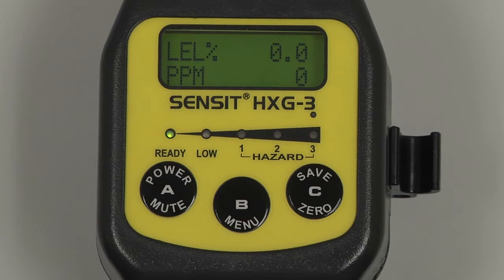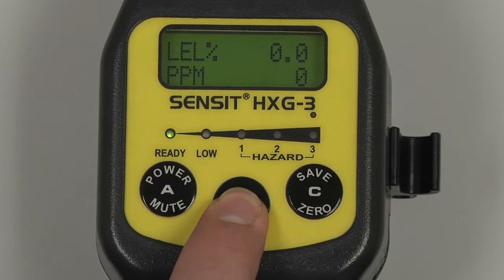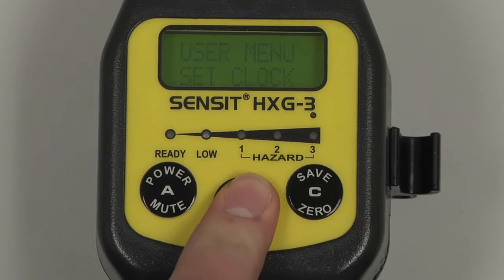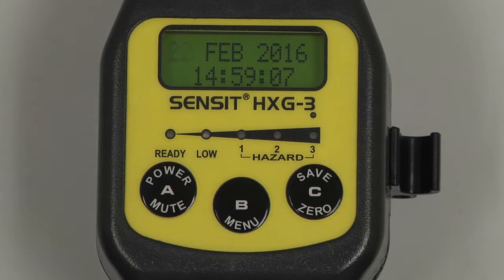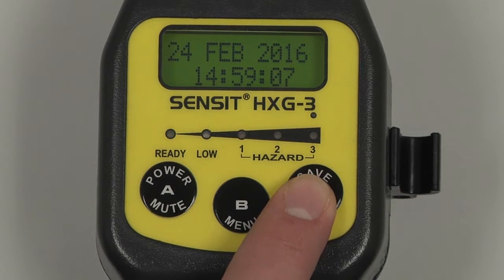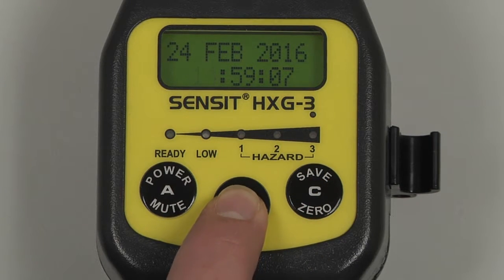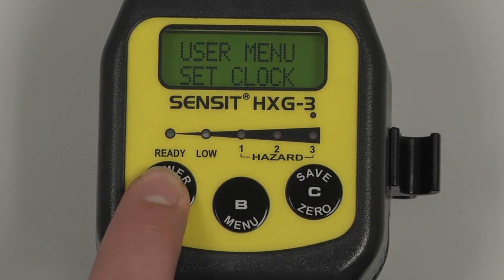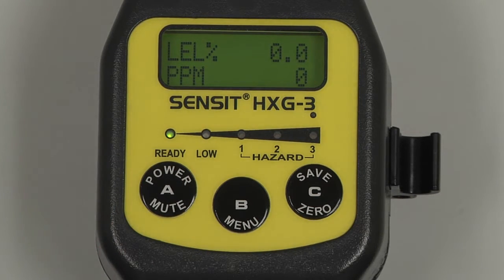Before calibrating, we must verify the date and time and perform a flow check. To verify the date and time, enter into the user menu by pressing and holding the B button, and scroll through the menu by pressing and releasing the C button until Set Clock appears. Select by pressing and releasing the B button, and the date and time will be displayed. If any adjustments are needed, you can increase the current field by pressing and releasing the B button, and scroll to the next field by pressing and releasing the C button. Once the date and time are correct, save by pressing and releasing the C button, and again to return to the working display. To perform a flow check, place a finger over the inlet at the end of the gooseneck until a flow block message appears.